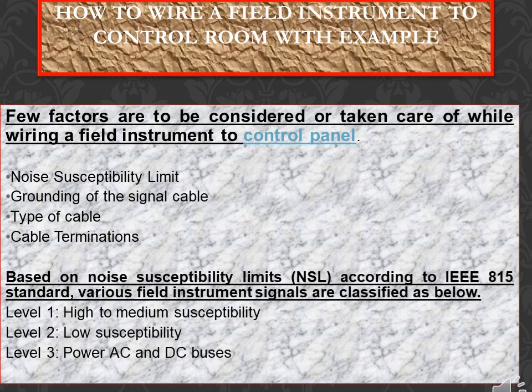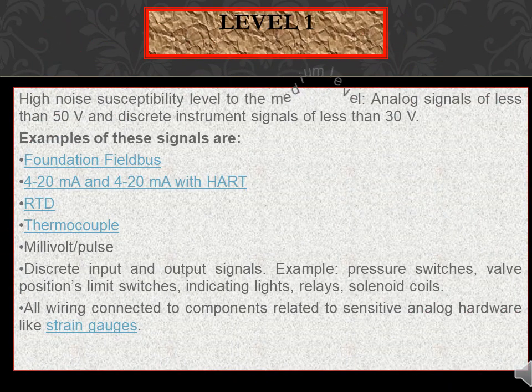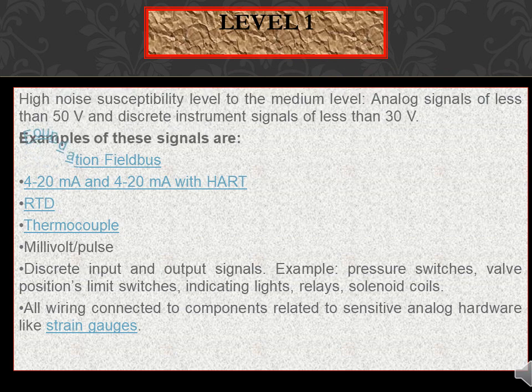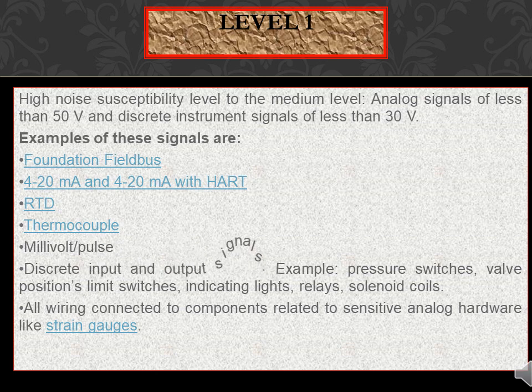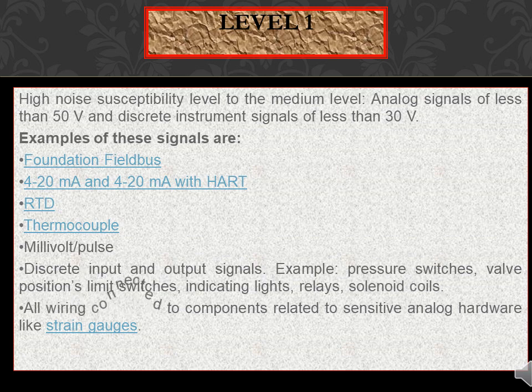According to IEEE 815, various field instrument signals are classified as follows: Level 1 — high to medium susceptibility; Level 2 — low susceptibility; Level 3 — power AC and DC buses. Level 1 covers high noise susceptibility signals, including medium-level analog signals of less than 50 volts and discrete instrument signals of less than 30 volts.